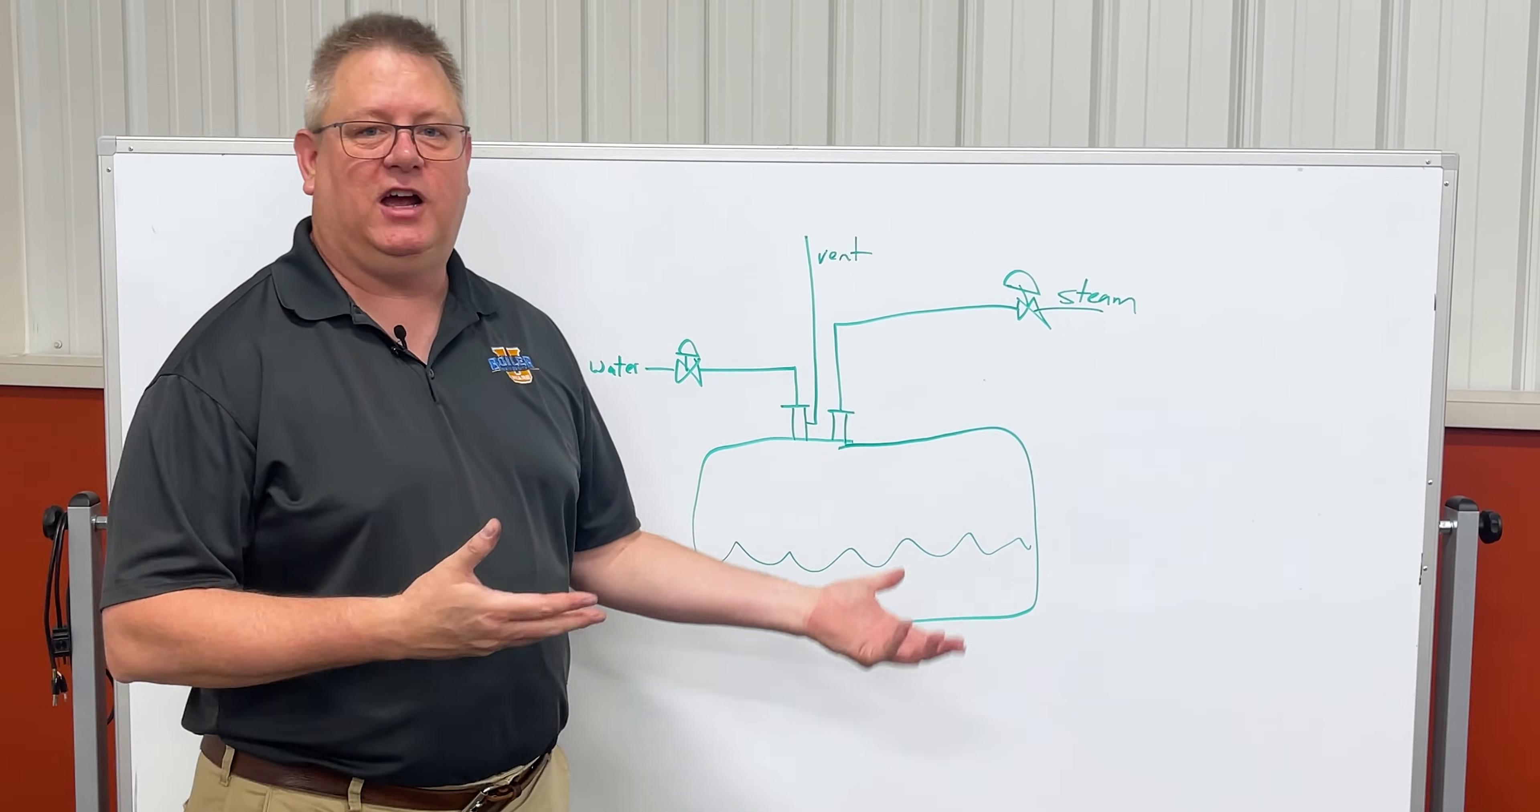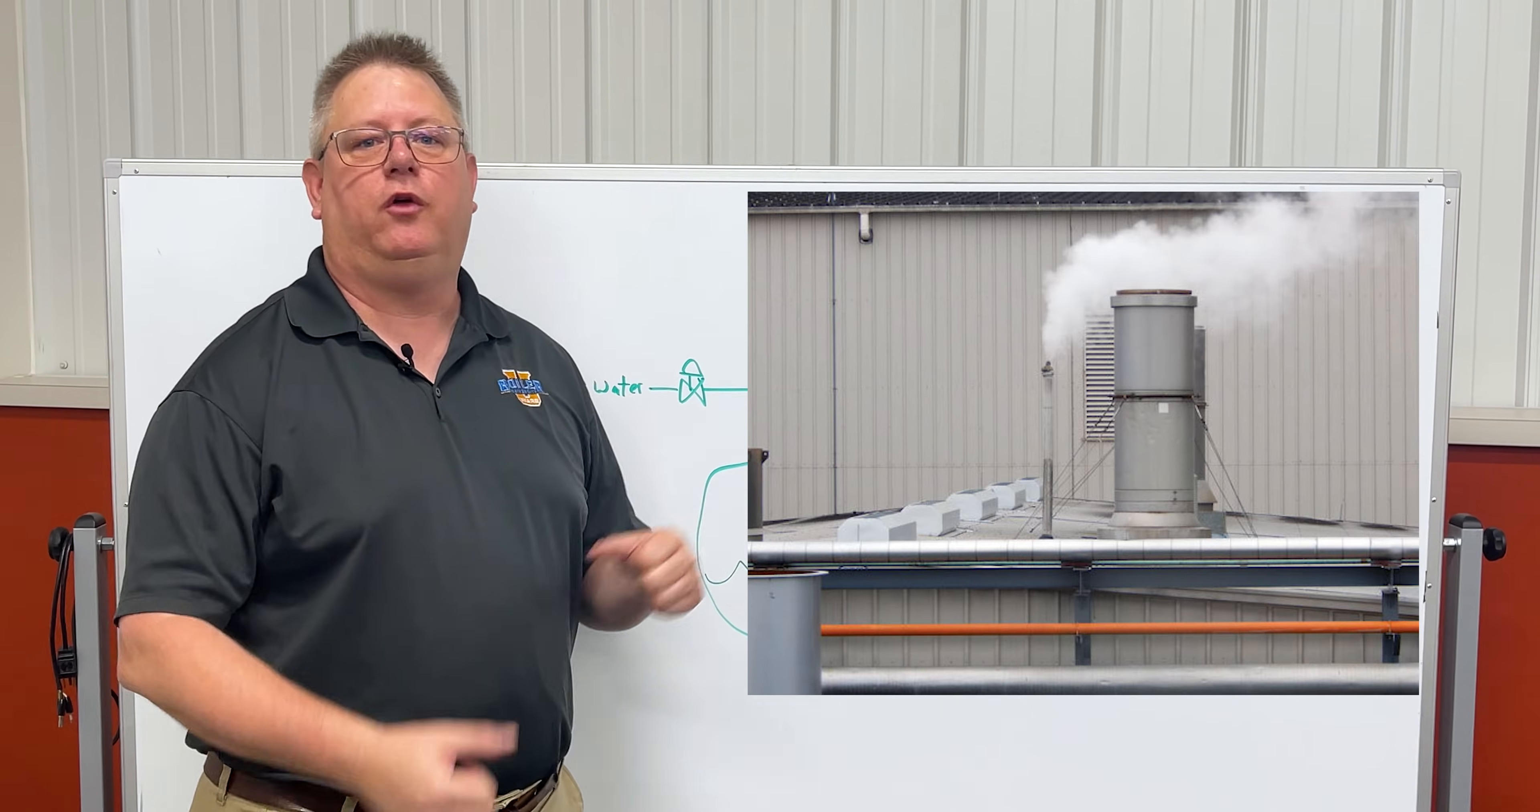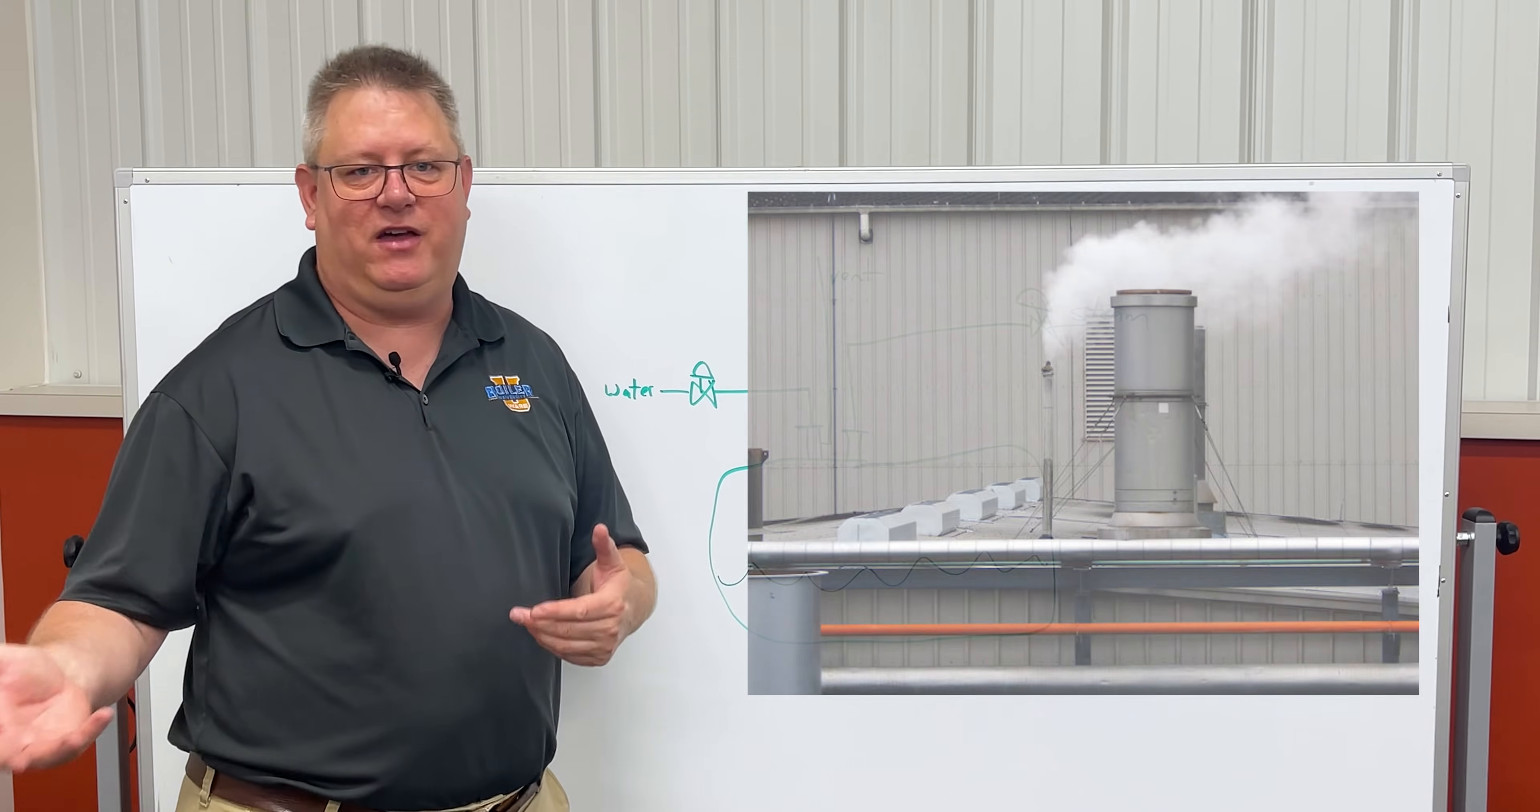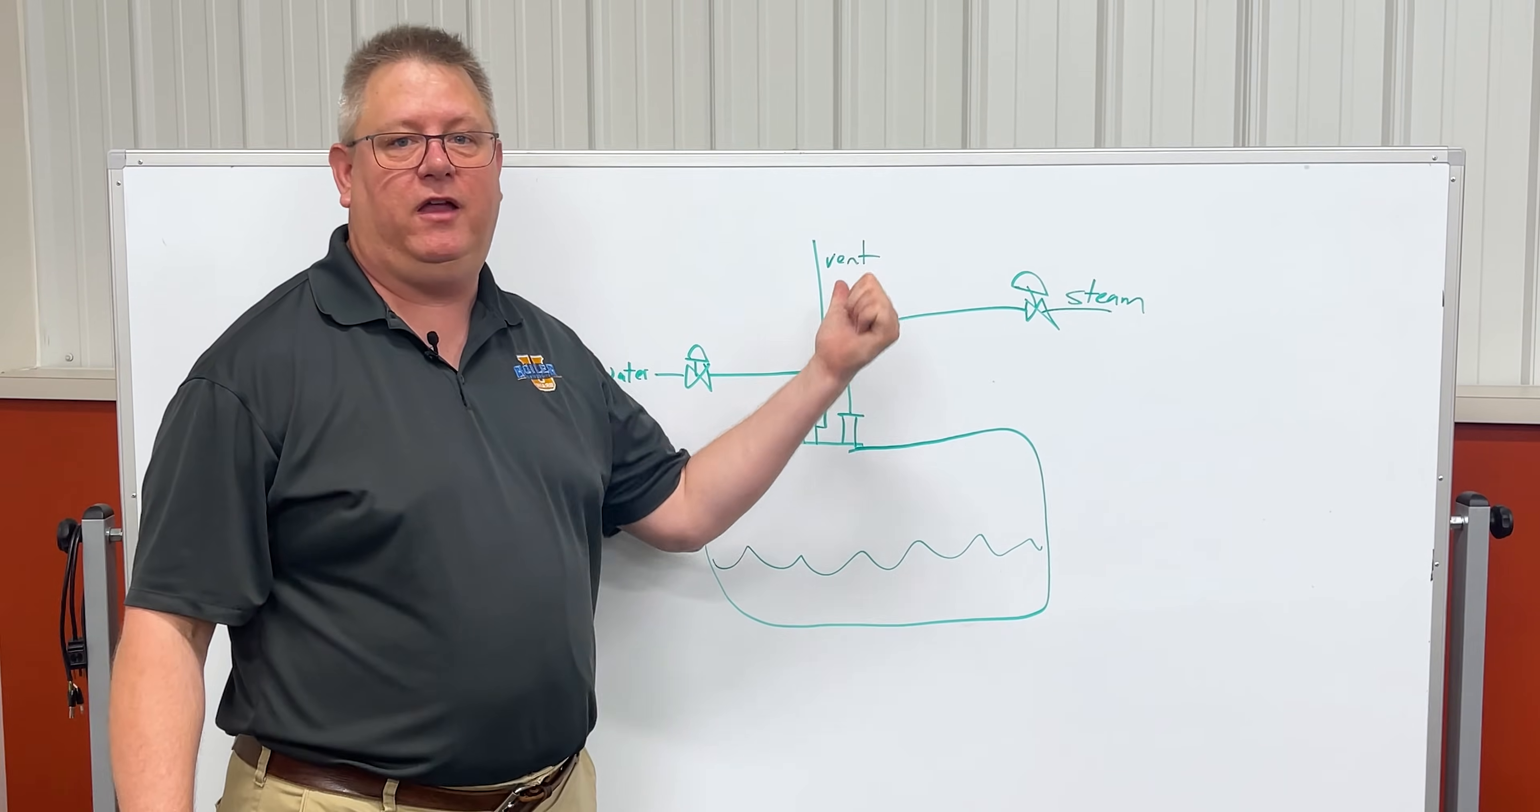One thing we're going to check on our deaerator is not actually inside the boiler room—we're going to check it on the roof. You may have to go up on the roof, or you may be able to see the vent from the ground somewhere, but we want to get a visual on this vent.